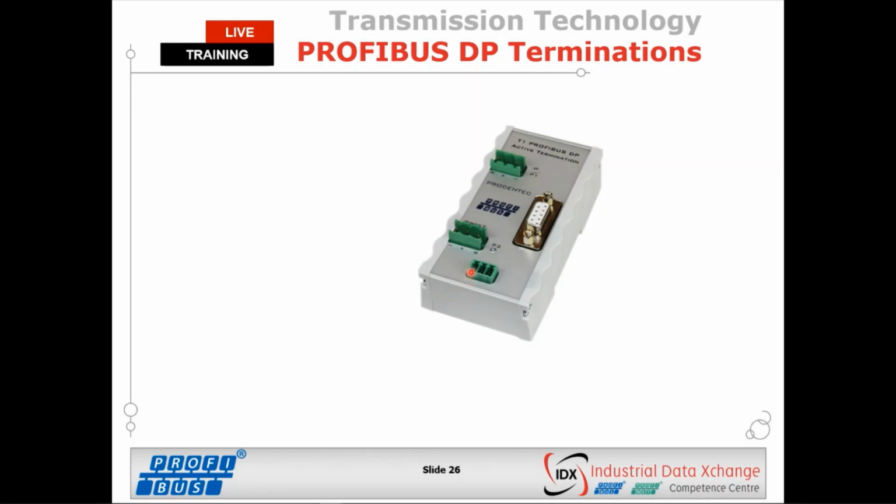You would typically wire your Profibus network into these bottom 3 pins and supply them with a dedicated power source. It also creates a connection point for your testing tool to be plugged into the network. It's very useful to have connection points in every single segment, because when you want to plug in a testing tool, you actually want to look at the true electrical quality of that segment itself.